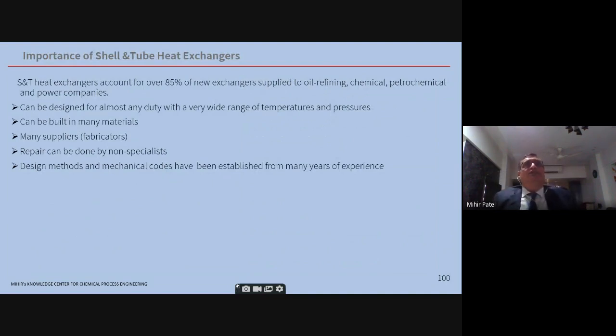So, shell and tube heat exchangers account for over 85% of new exchangers. Now, there are many reasons for this. It can be designed for almost any duty with a wide range of temperatures, pressures. It can be built in many materials. Many fabricators and suppliers are there, so you don't have a scarcity, and a lot of bargaining can be done. You can get the equipment at a cheaper, competitive rate. Repair can be done by non-specialists, and design methods and mechanical codes have been established over many years of experience. You have good software in the industry. HTRI is the premium software for design of this, and it gives an excellent design. It directly gives a TEMA datasheet also as an output.